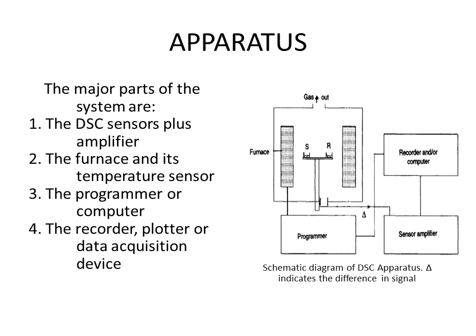Here is the instrumentation of DSC. In the schematic diagram you can see the sample pan, the reference pan, and the furnace or heaters — which may be individual or common for sample and reference. The temperature in the pans and the atmosphere in the compartment can be controlled by adding or removing gas. A programmer controls the temperature program, and the differential signal Delta is sensed, amplified, and recorded by computer devices.